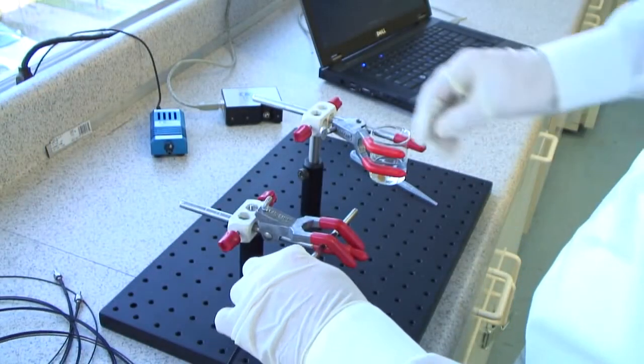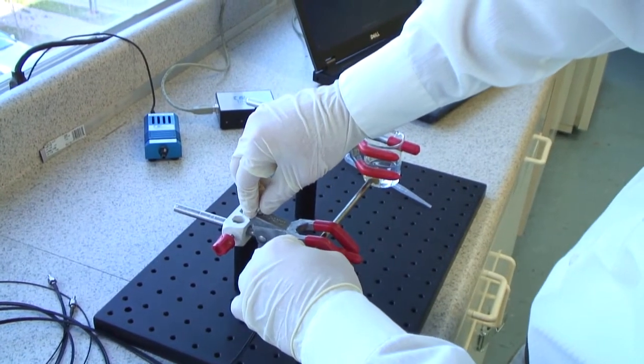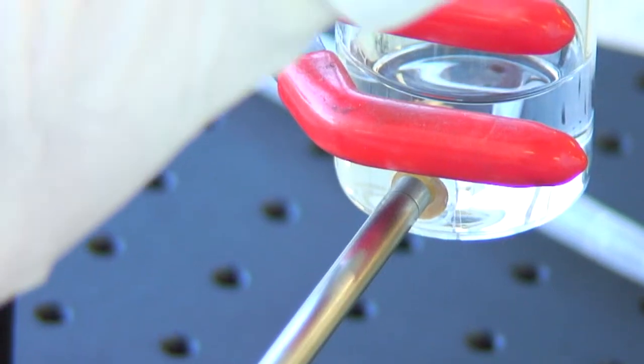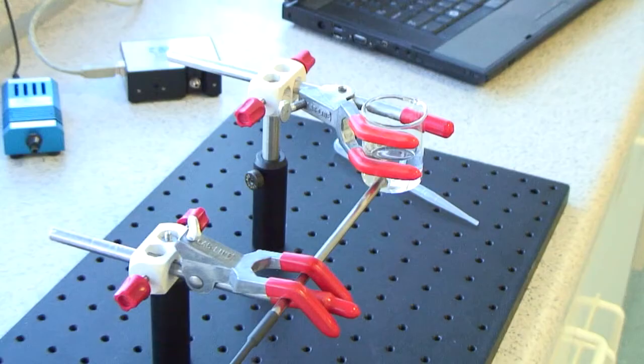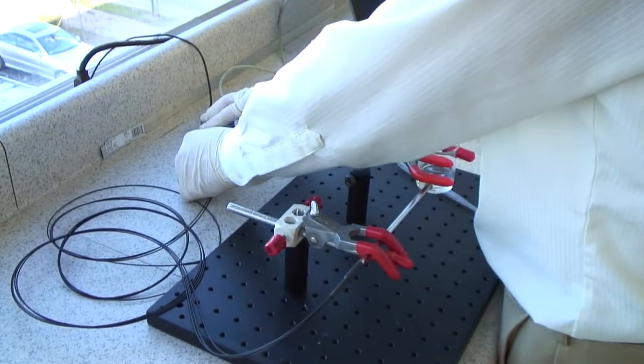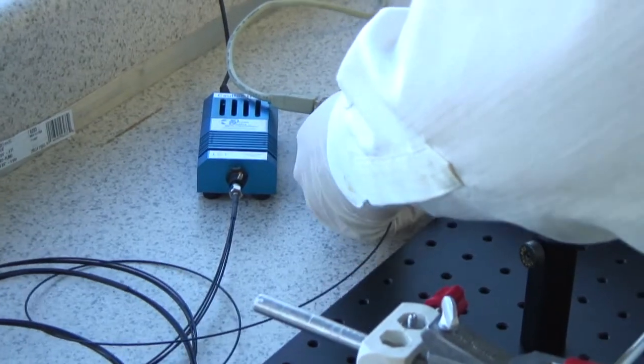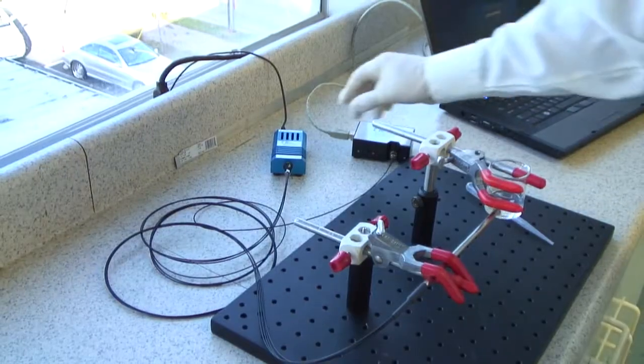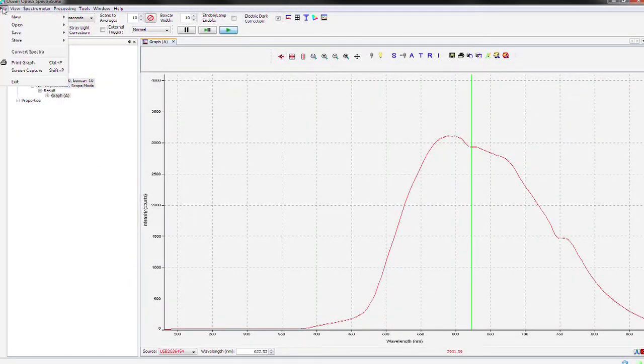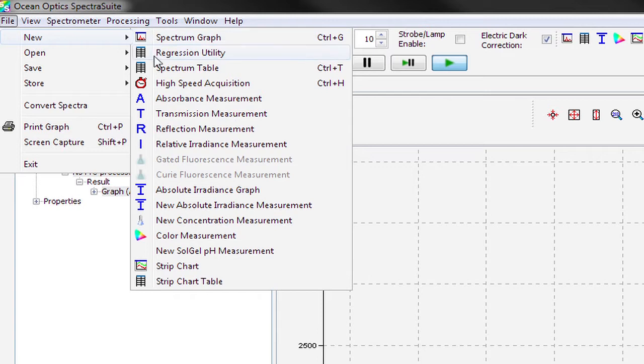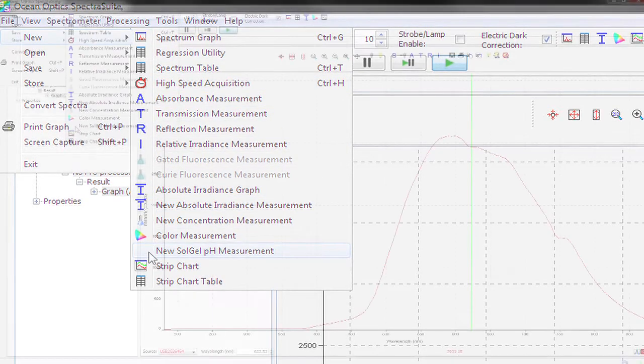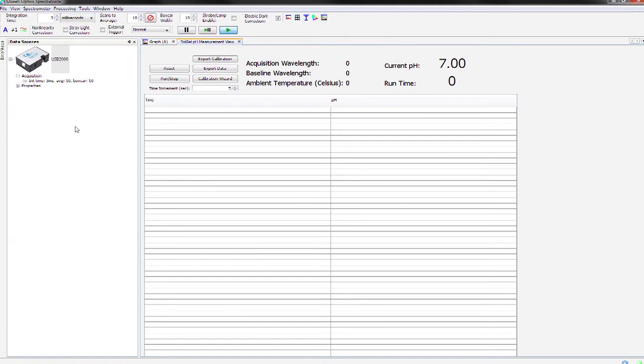Next, secure the probe flush against the wall of the vessel, with it aimed directly at the center of the sensor patch. The thickness of your vessel wall will determine sensor resolution. Connect the illumination leg to the light source, and then the detection leg to the spectrometer, and turn on your light source. Open SpectraSuite and select File, New, and then New Sol Gel pH Measurement. This will bring up the pH module. This module has to be added to SpectraSuite and can be found on the Ocean Optics Sensors technical site.